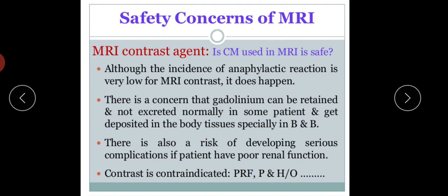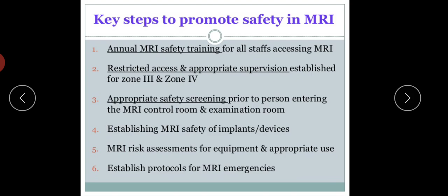Now, key steps to promote safety in MRI: annual MRI safety training for all staff accessing MRI; restricted access and appropriate supervision established for zone 3 and zone 4, that is dividing the MRI into various zones; appropriate safety screening prior to a person entering the MRI control room and examination room; establishing MRI safety of implants and devices; MRI risk assessment for equipment and appropriate use; and establishing protocols for MRI emergencies.